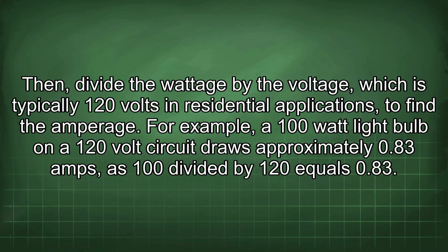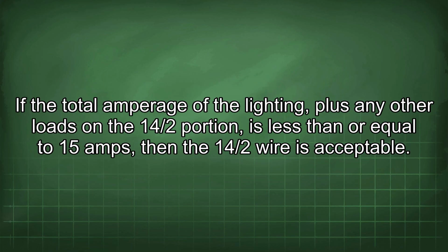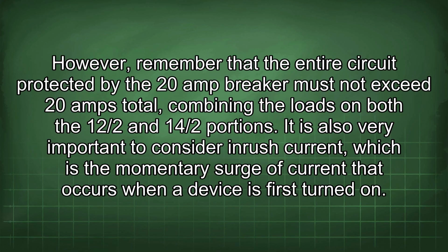For example, a 100-watt light bulb on a 120-volt circuit draws approximately 0.83 amps, as 100 divided by 120 equals 0.83. If the total amperage of the lighting, plus any other loads on the 14/2 portion, is less than or equal to 15 amps, then the 14/2 wire is acceptable. However, remember that the entire circuit protected by the 20 amp breaker must not exceed 20 amps total, combining the loads on both the 12/2 and 14/2 portions.